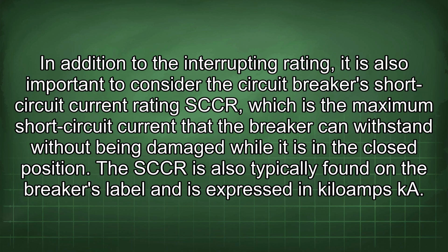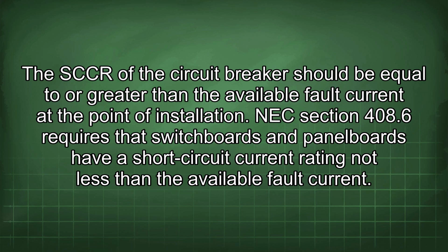In addition to the interrupting rating, it is also important to consider the circuit breaker's short circuit current rating, SCCR, which is the maximum short circuit current that the breaker can withstand without being damaged while it is in the closed position. The SCCR is also typically found on the breaker's label and is expressed in kiloamps, kA. The SCCR of the circuit breaker should be equal to or greater than the available fault current at the point of installation. NEC Section 408.6 requires that switchboards and panelboards have a short circuit current rating not less than the available fault current.